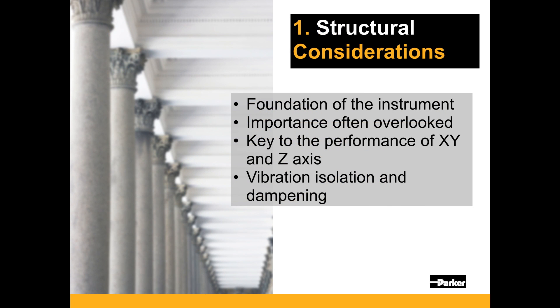The structure for the digital pathology instrument is the foundation for the machine's performance and capability. The structure can sometimes be overlooked when one tries to drive down the cost and size of the instrument. The structure provides a stiff backing to the X-Y stage as well as the Z-axis. In addition to stiffness, this structure must also incorporate vibration isolation and potentially dampening elements.